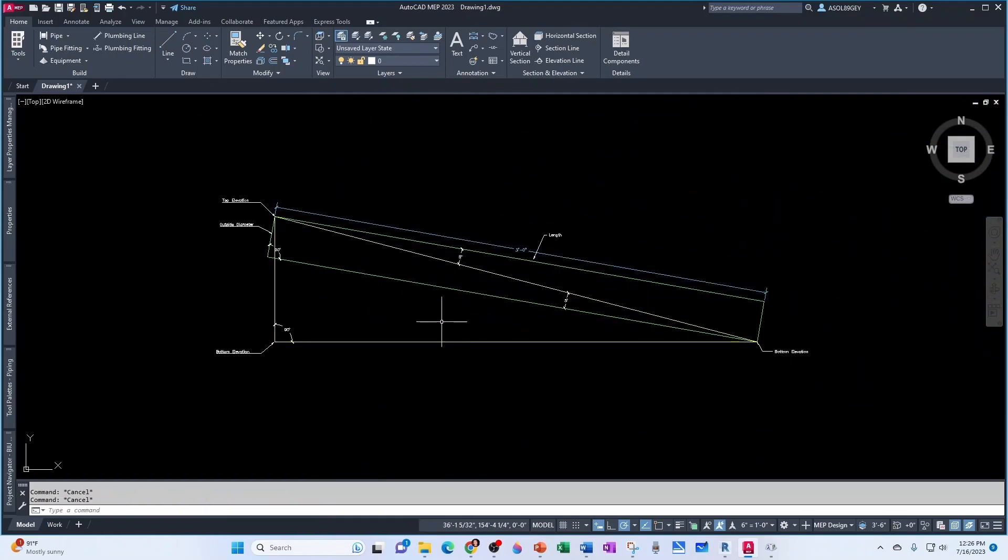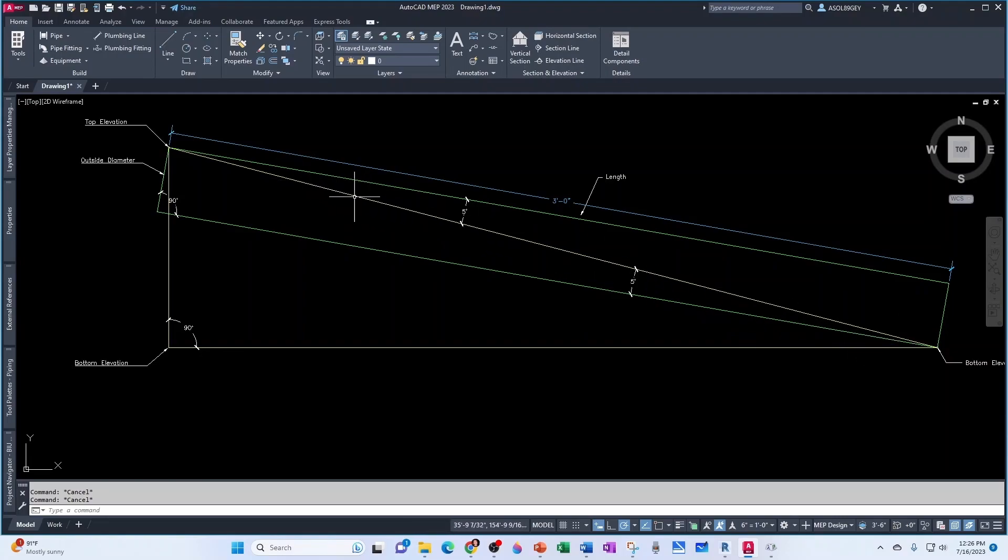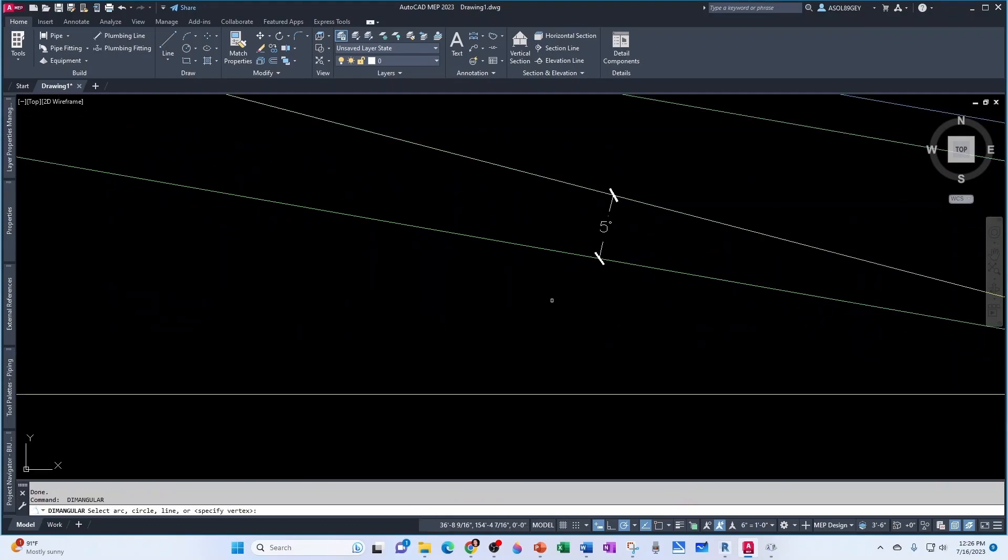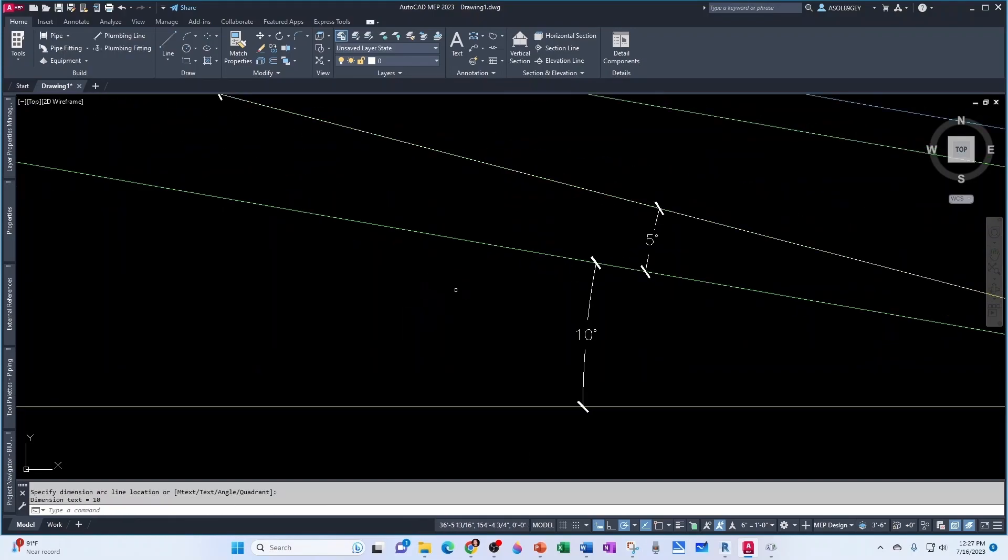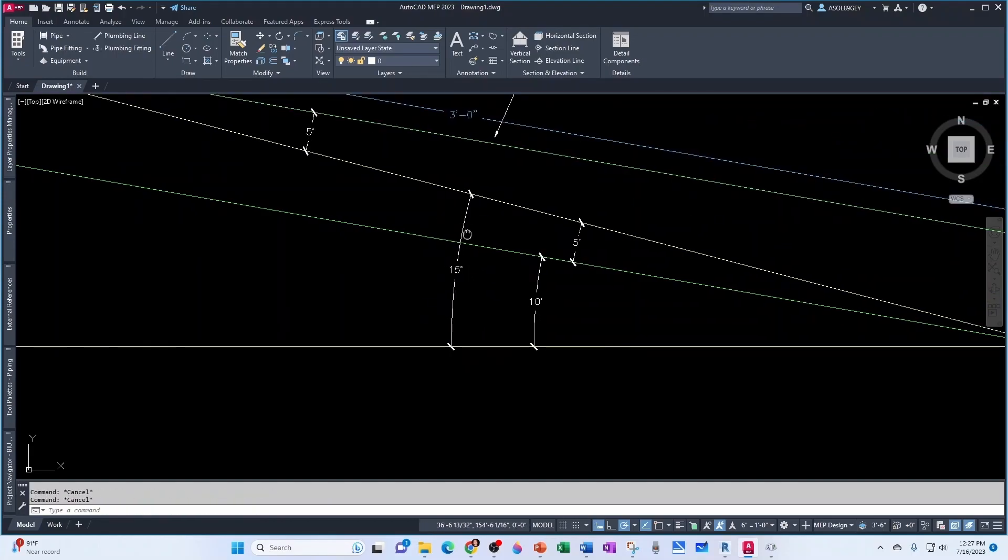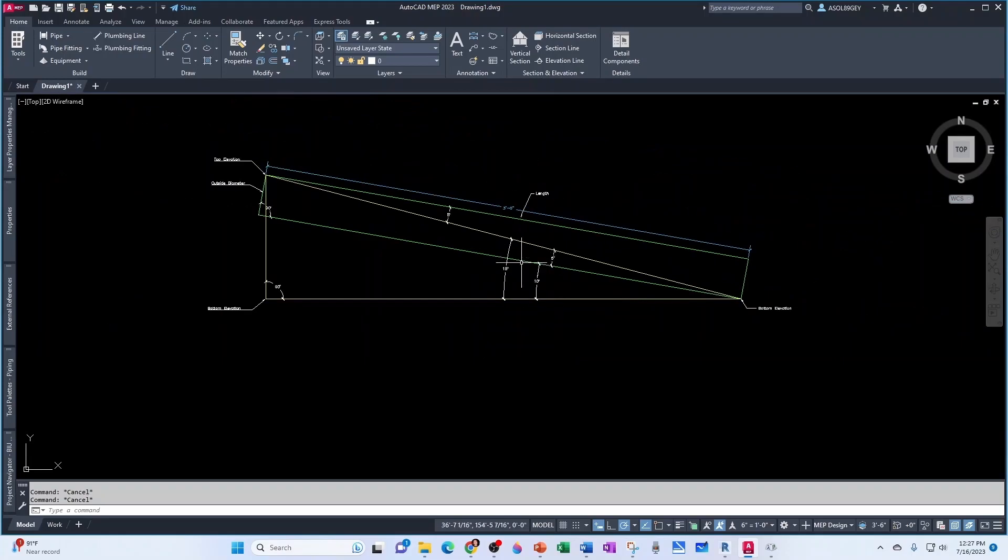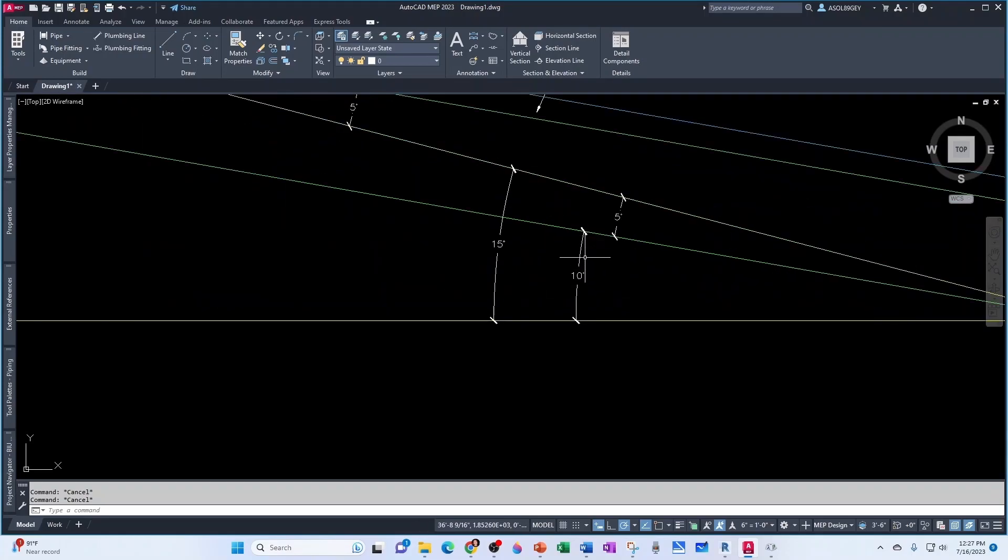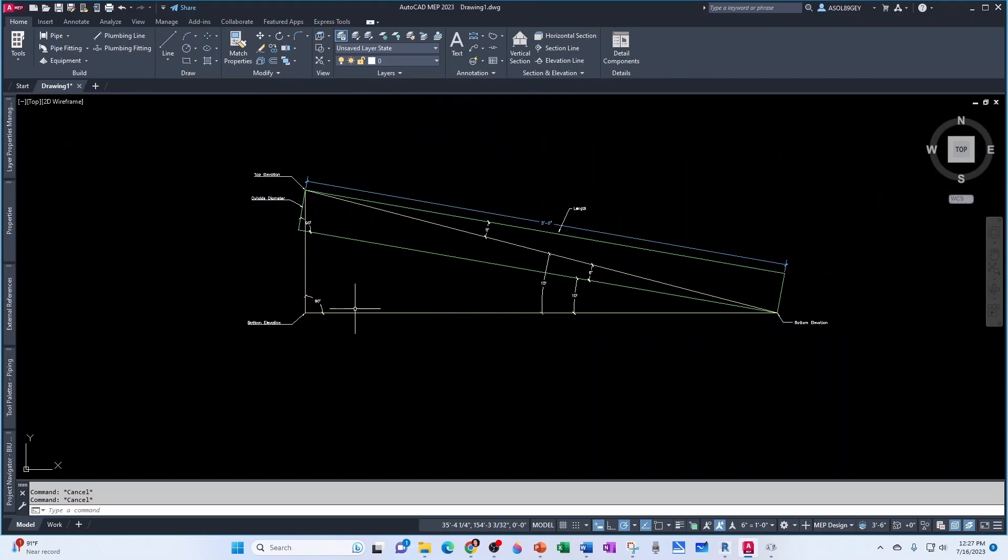And now notice that those two triangles, this yellow triangle and this green triangle share the same hypotenuse, which is this line right here. So I'm going to take advantage of that fact. And let's brainstorm a little bit. If I dimension this here, from here to here, I know that this angle here, from here to here, is going to be equal to this angle plus this angle. So the angle that I'm interested in is this one down here, because that's the angle between the horizontal plane and our pipe. So that's the slope of our pipe.